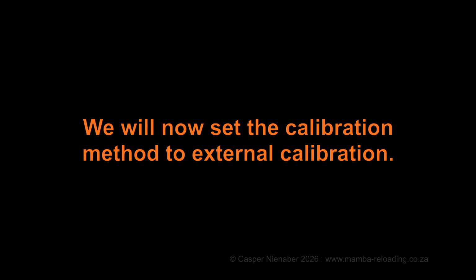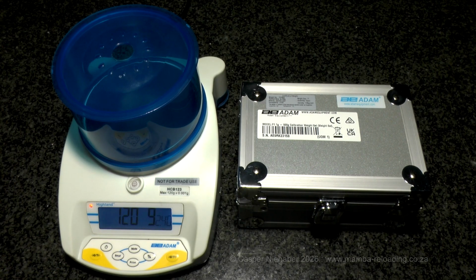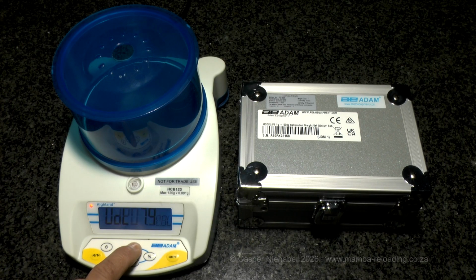We will now set the calibration method to external calibration. Press the On button and hold the Mode button until F1 UNT is displayed. Press the Mode button repeatedly until F5 IEC is displayed. Press the yellow Zero/Tare button. INT internal is shown. Press the Mode button to select E external calibration and save it by pressing the yellow Zero/Tare button. Press the Print button to exit the calibration selection menu and return to the normal weighing mode.